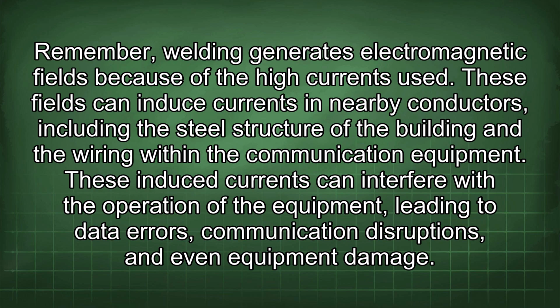Remember, welding generates electromagnetic fields because of the high currents used. These fields can induce currents in nearby conductors, including the steel structure of the building and the wiring within the communication equipment. These induced currents can interfere with the operation of the equipment, leading to data errors, communication disruptions, and even equipment damage.